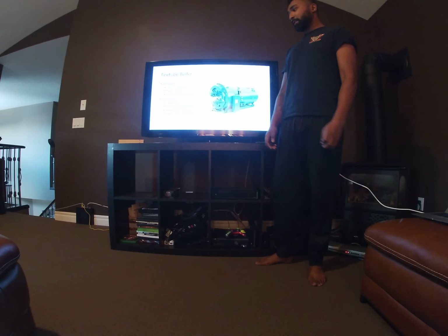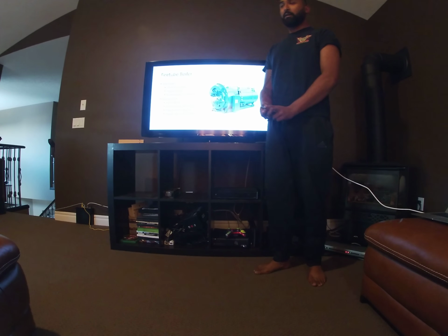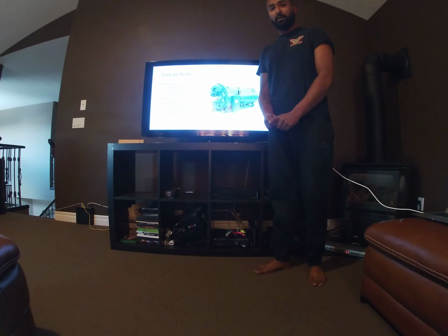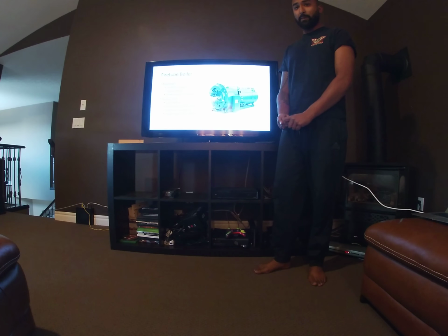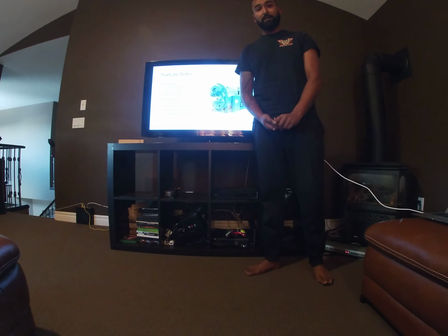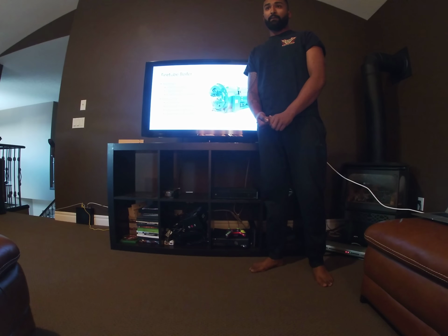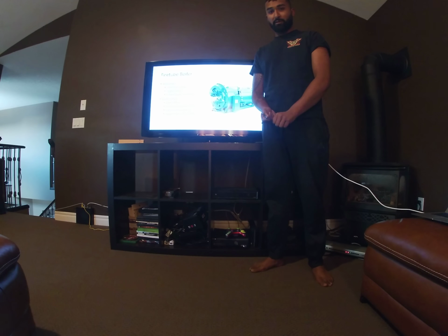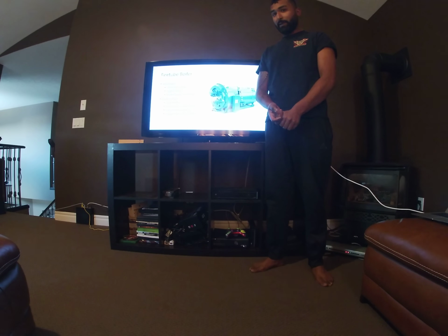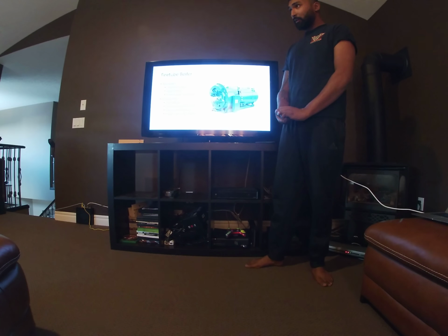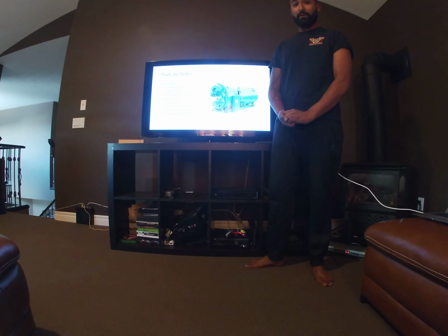The disadvantages of these fire tube boilers would be that they have a very slow startup because of the amount of water in them. It's not as safe as the other boilers, but it is still safe. The fire tube boilers have a limit to low pressure, so they're only good for low pressure capacities. They also require special concrete foundations.